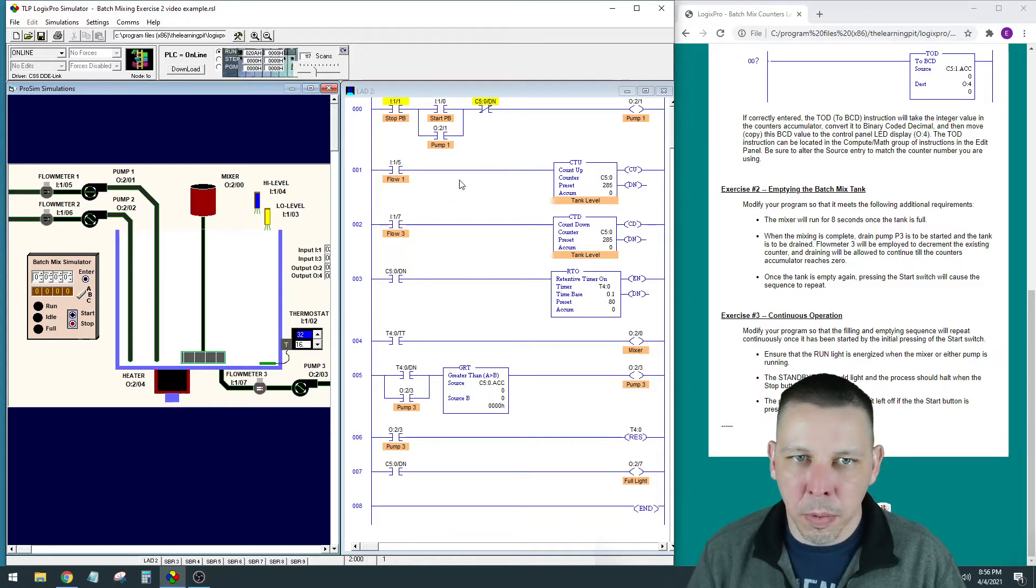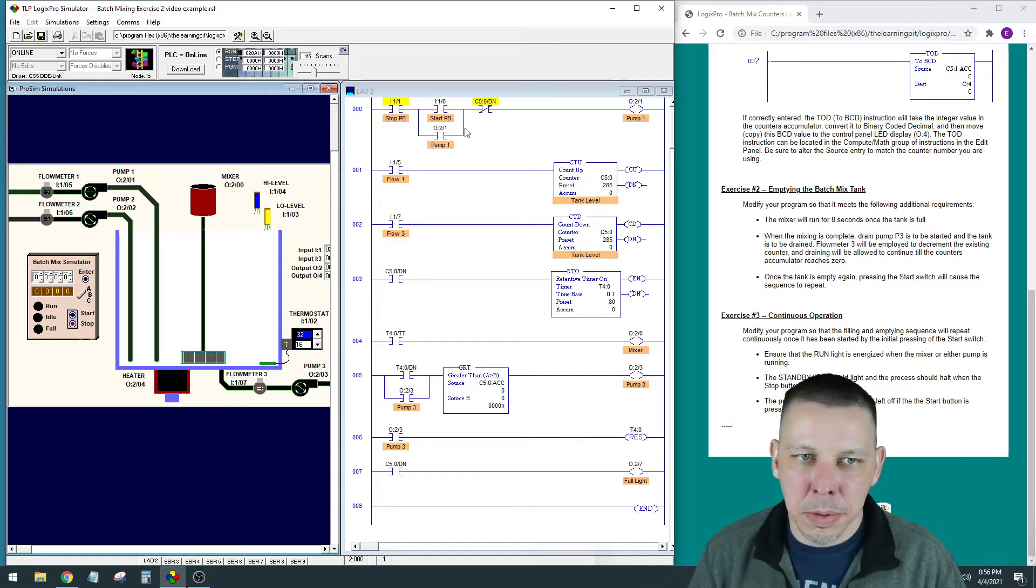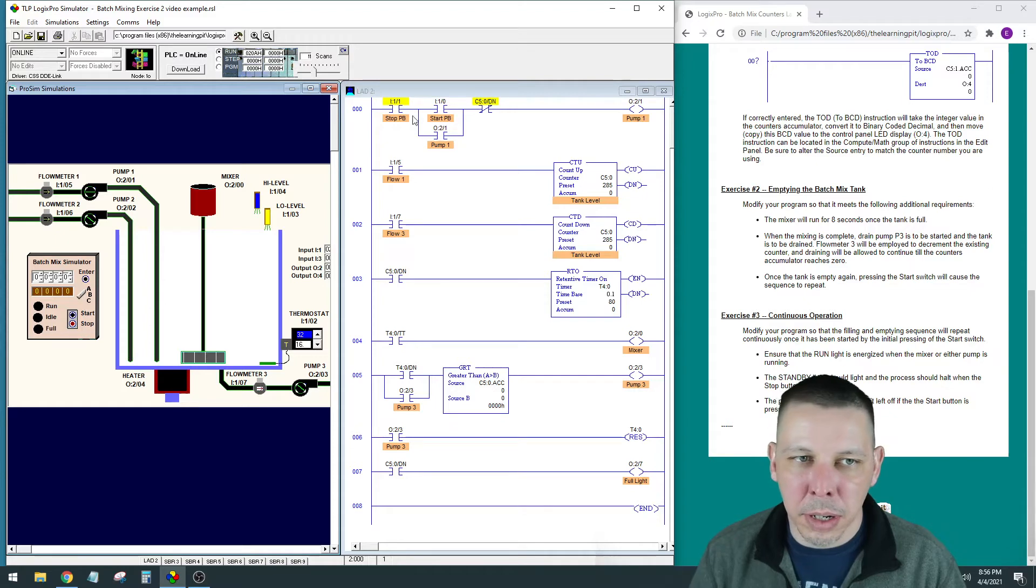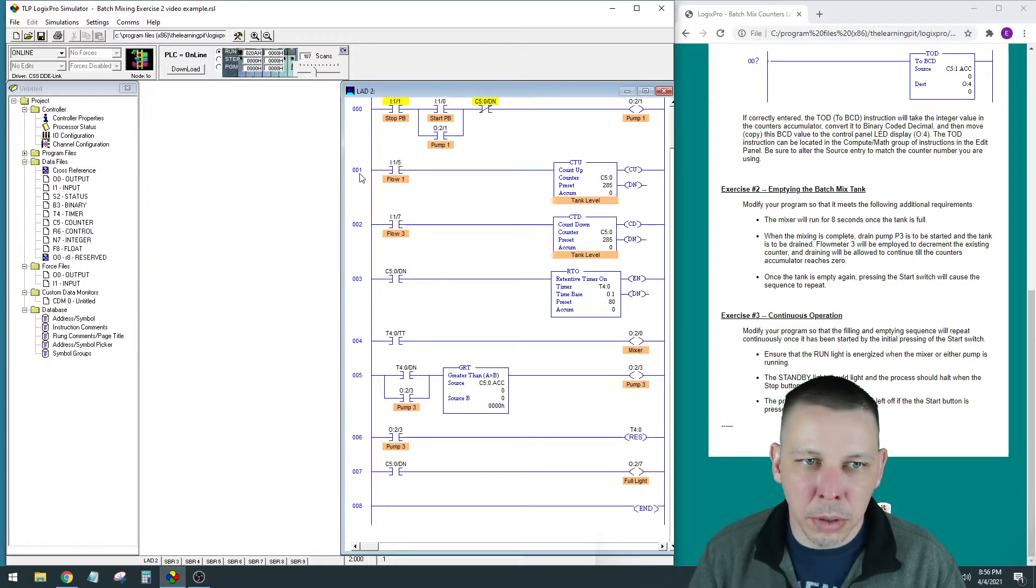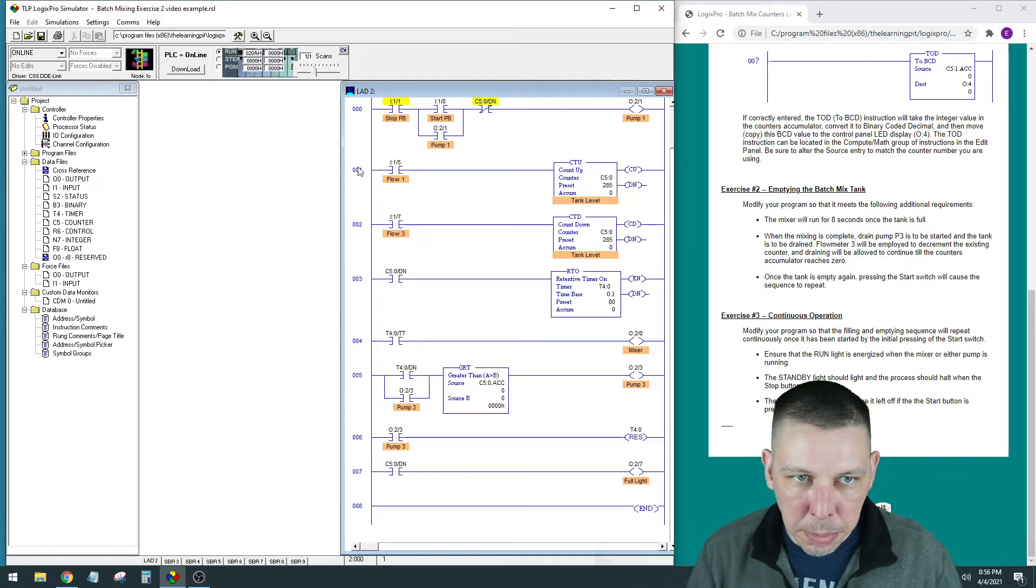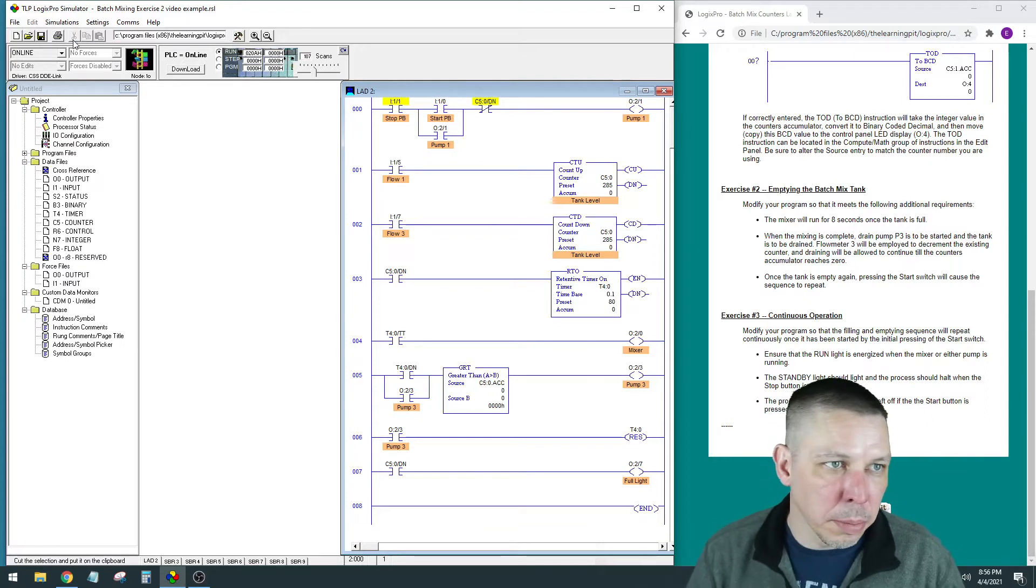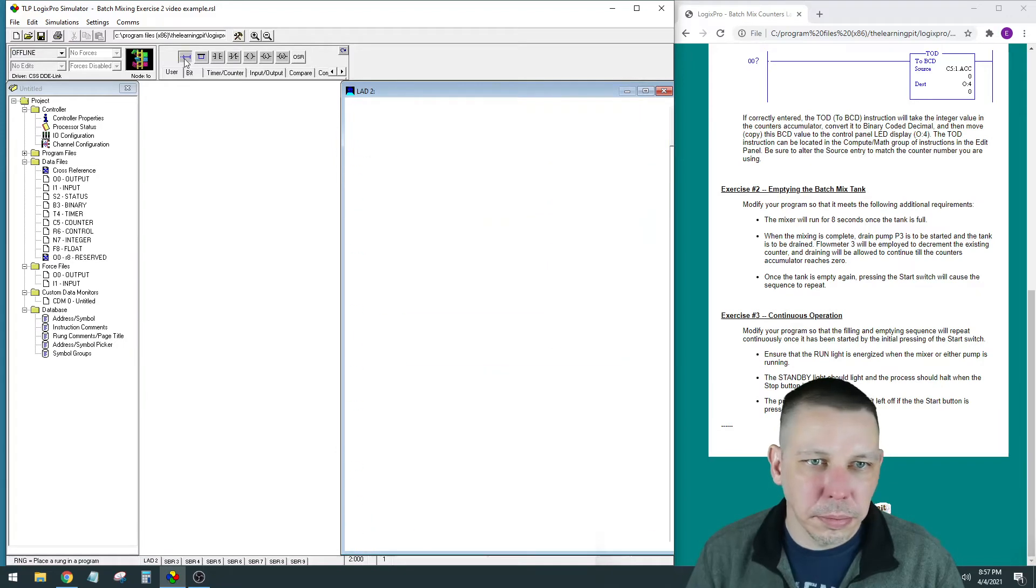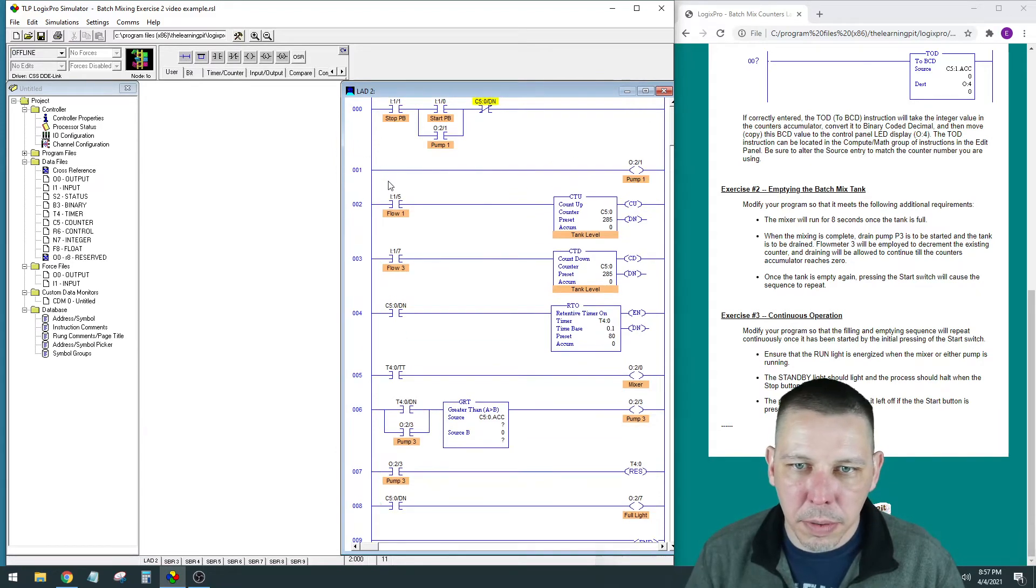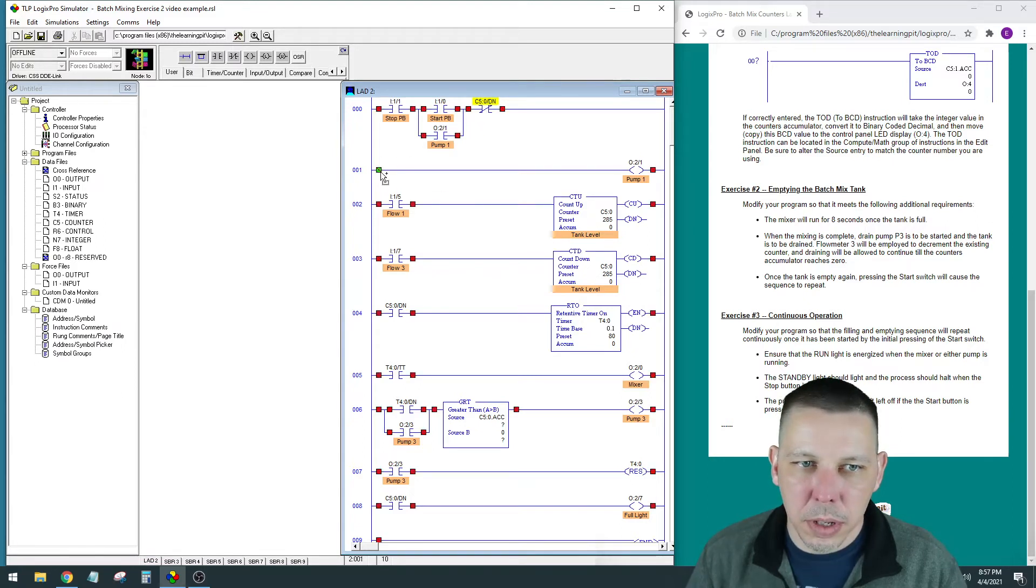For this, I am going to have the stop/start not run the pump directly. The stop/start button is going to have to affect a few different things, so I'm going to have to put another bit in here, a memory bit. I will put a rung down here underneath to put that pump in.